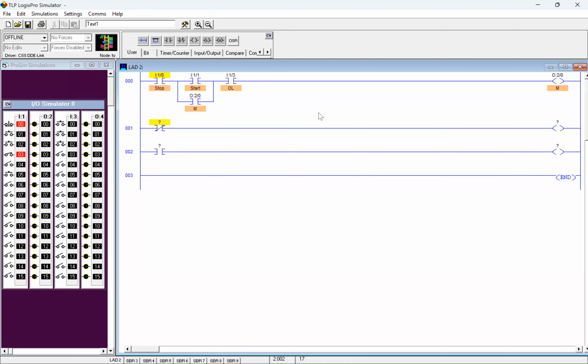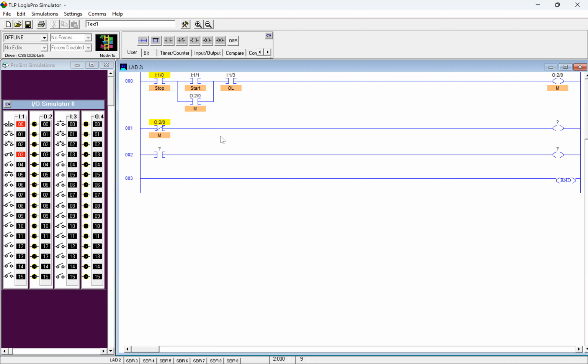And the key behind this is that these are also associated with this. So I can just drag that address down. I don't need another control relay. This is the beauty of the PLC. I eliminated wiring an entire set of control relays to do this. That's the beauty of this. This is the key right here. Yeah, that takes the five walls in your room there of relays and brings it down to one PLC. I mean, huge difference. And troubleshooting is 10 times faster, 100 times faster.